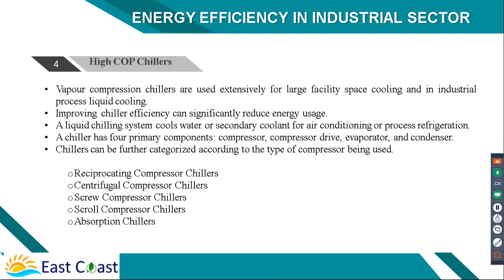Now we are talking about chillers, High COP chillers. If you look at LEED standards for buildings, High COP is defined as more than 5 - if a chiller's coefficient of performance is more than 5, it's called a High COP chiller. Under ECBC codes and other rating systems, these are mandatory. So whenever you're buying chillers, you can consider this.